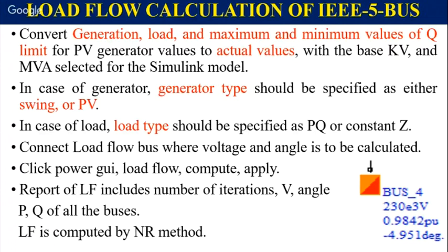Before simulation, you convert all the per unit values of transmission line parameters into actual values, because in the Simulink model we want actual value per kilometer. Then convert generation, load, and the maximum and minimum reactive power limit for the PV generator to actual values, because generation and load are also given in per unit. Suppose it is given as 0.5 per unit, you have to convert it using the base MVA. If you take base MVA as 100 MVA, then 5 into 100 will give 500. So you have to convert the actual values of load, generation and the reactive power limit for the PV generator, so that you can enter them in the Simulink model.